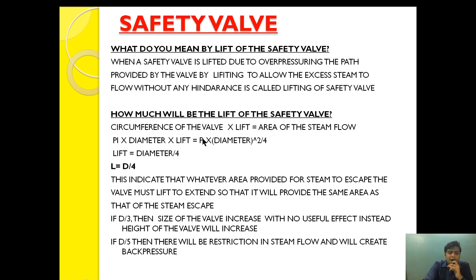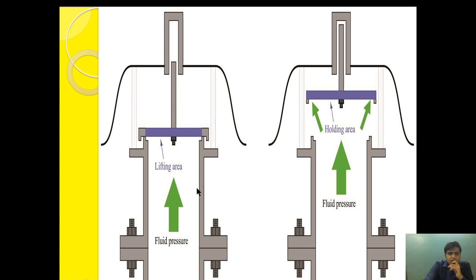The area of the steam flow is πr², which in diameter form is πd²/4. So we have 2πr × L = πr². Cancelling π from both sides and simplifying, we get: L = d/4. So lift L equals diameter divided by 4, or equivalently radius divided by 2.